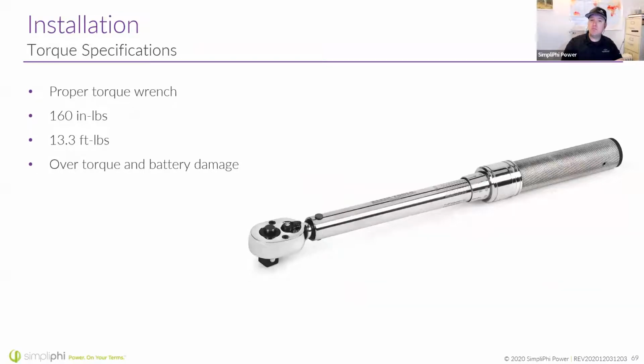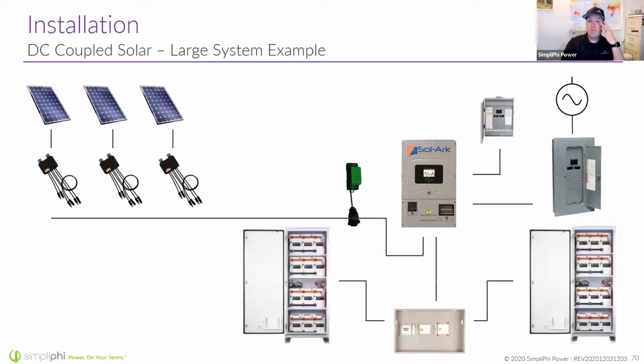Please, when you're tightening down the battery lugs, don't let one of your technicians go to town with an impact driver on them. Go out to the van and get your torque wrench. 160 inch-pounds is what I want to see on your torque wrench. Ideally that would be an insulated torque wrench, but remember, we have breakers built into the battery, so you can turn the battery off and know you're not going to get a big pop if you short it out. We're going to run through some examples really quickly.